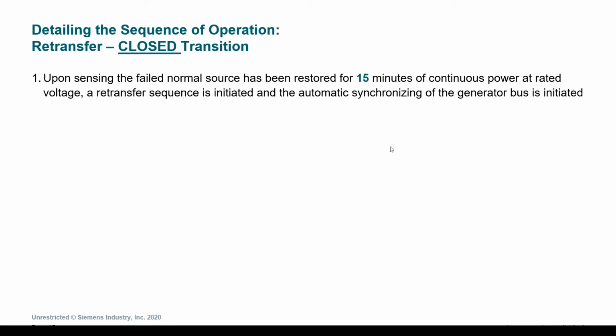But upon sensing the failed normal source being restored for 15 minutes of continual power at that rated voltage, the retransfer sequence is initiated and that automatic synchronizing of the generator bus is initiated. It is important to mention that that 15 minutes of continuous power at the rated voltage is programmable. 15 minutes is typical. However, it can be shorter or longer based, again, off the utility's requirements or the facility's request. After that's complete, synchronizing is verified across the transfer switches, the life safety, the critical, and the equipment in a hospital application.